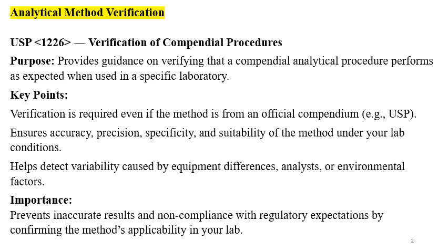USP chapter 1226 provides the verification of compendial procedures and guidelines. The purpose of analytical method verification is to verify that the compendial analytical procedure performs as expected when used in a specific laboratory. And this USP chapter provides guidance for method verification.